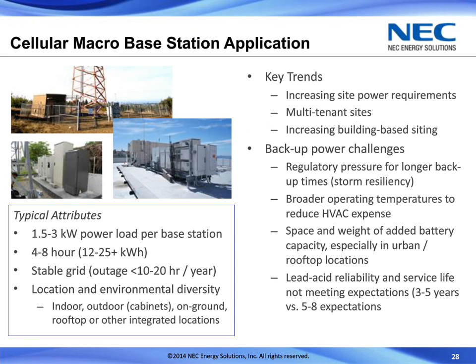Okay, so the first application is Cellular Macro Base Station. A key trend in this area is increasing site power requirements. So, a lot of batteries being added to meet the increased power requirements. Some backup power challenges in this area include regulatory pressure for longer backup times, for storm resiliency, for example. So for this reason, people are adding batteries as well. So for the increased power and for the increased energy. Broader operating temperatures due to reduced HVAC expense. So people are trying to push the envelope on the temperature range in the batteries, and if the batteries can handle it, then you don't need the HVAC infrastructure to control the temperature.